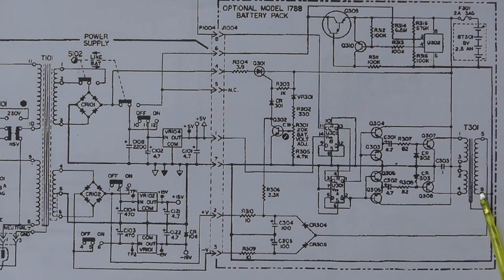Here you can see the AC output from the inverter being rectified by these two diodes here, and then being smoothed, and then those positive and negative voltages, the higher voltage there, are fed to the plus and minus 15 volt regulators to then feed the 15 volts to the main printed circuit board. So there you have the battery pack circuit, which is actually used on a number of the Keithley meters. So you'll see this circuit used on several Keithley meters of this same vintage.